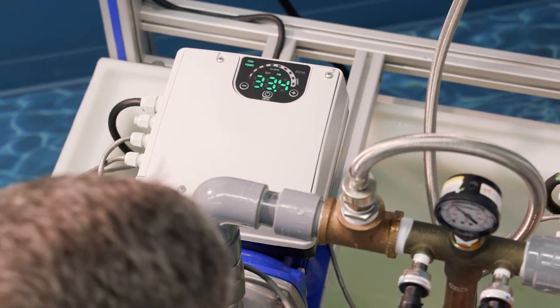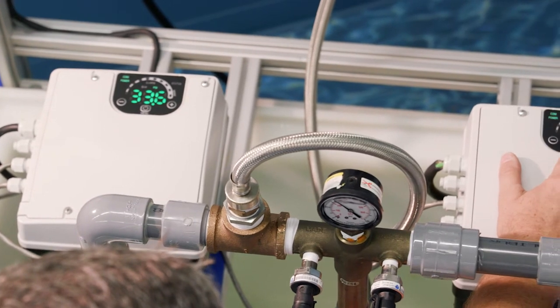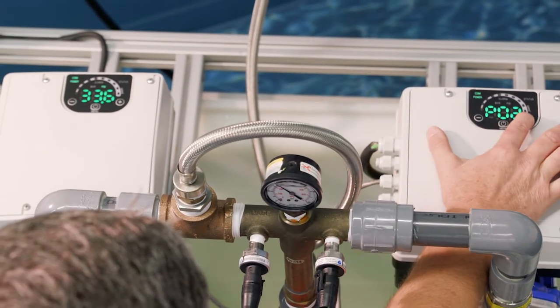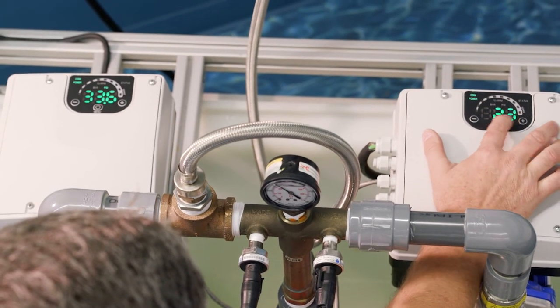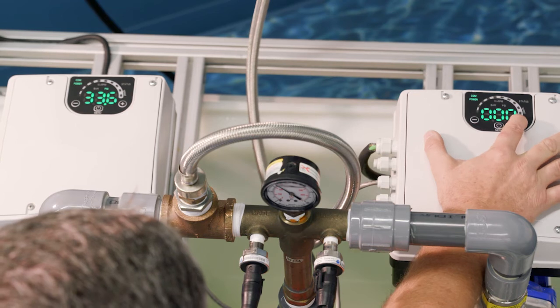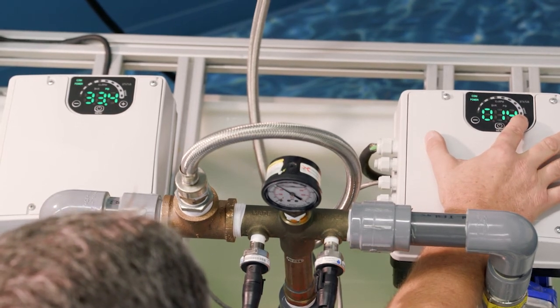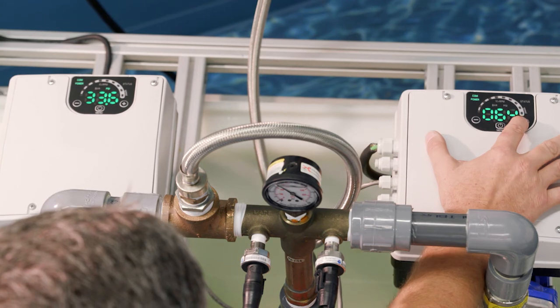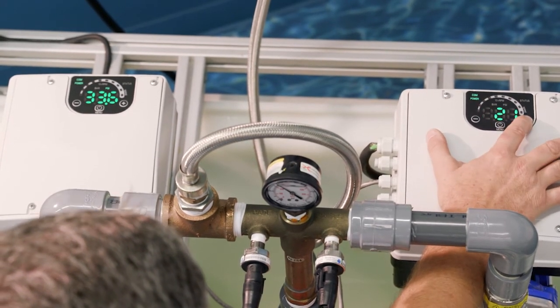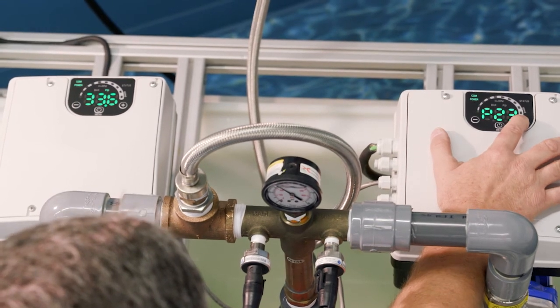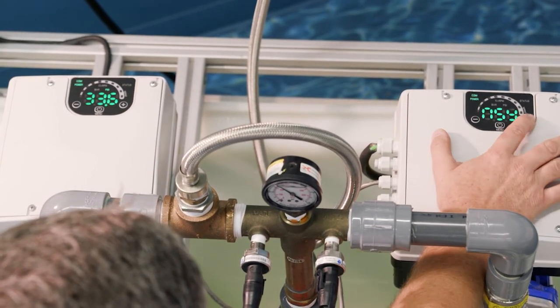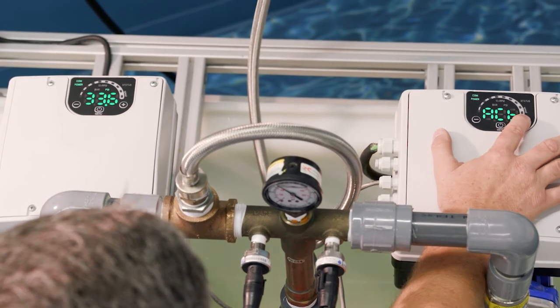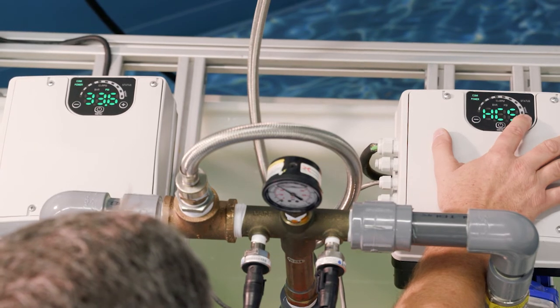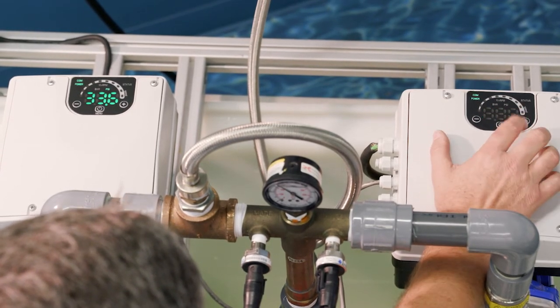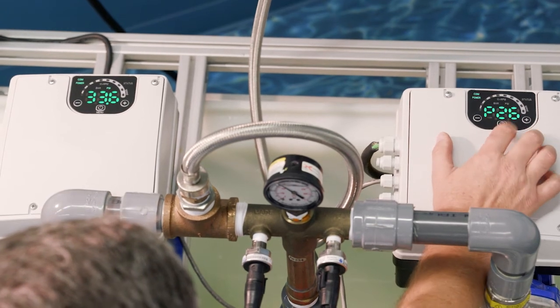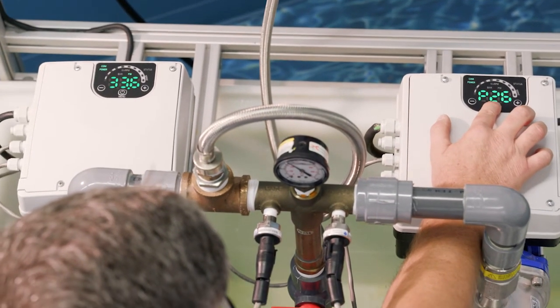So we just have to do the same thing over here. So press and hold, gets us to the parameter. Let's go and just put our password in again just in case we need it. So that's 66. Allows us to go to parameters greater than P20. P25 again, and we just need to match them up. So there's actuator again, HCS, that would be your single pump, and here's our serial cascade. So press and hold, and now we're back to the main menu.